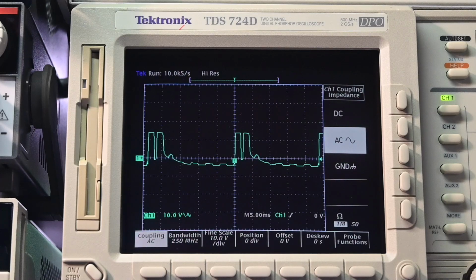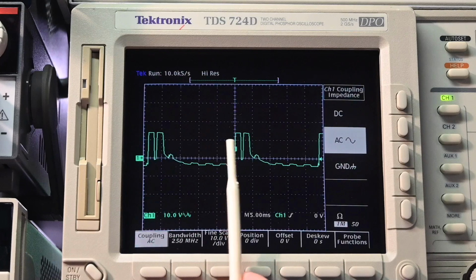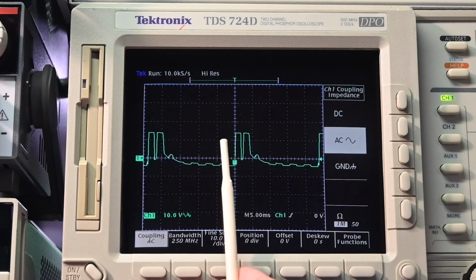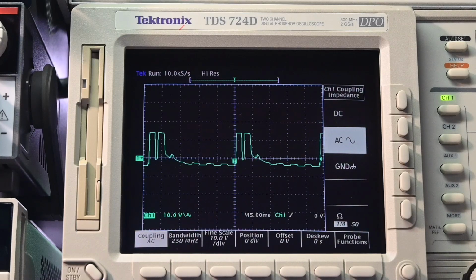All right, so the Fluke 8125A is powered up, and I have a DC voltage connected to the input, but the display is very random and it's just jumping around like we saw earlier in the video. Now the oscilloscope is connected to test point number 3, and the ground is connected to test point number 1. So you can definitely see on this waveform there's some issues going on. It doesn't really look like the waveform that's shown on that schematic. So for one thing, this pulse right here has a big spike that drops down in the middle, so it almost looks like 2 separate pulses, so that spike in the middle shouldn't be there.